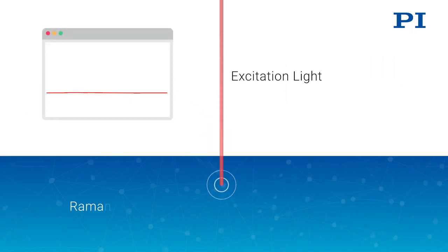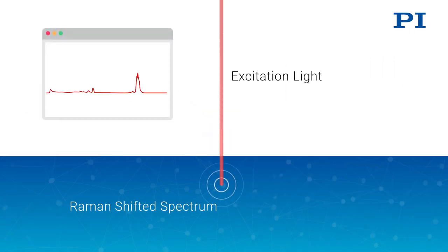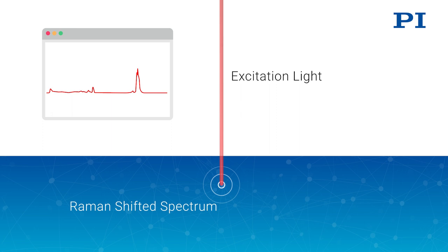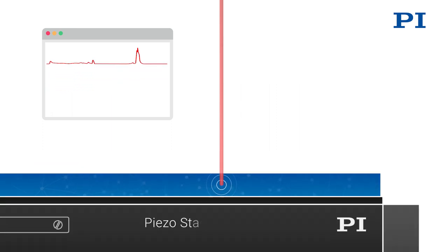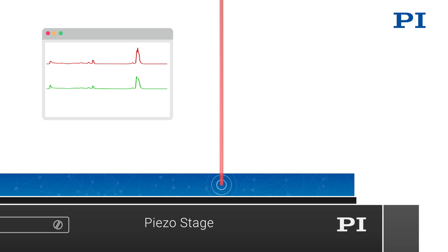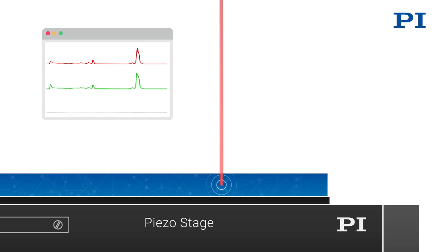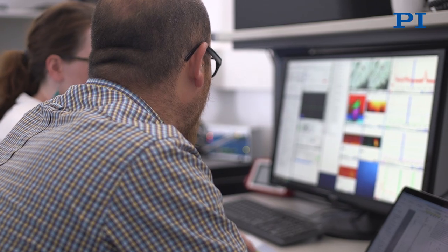In the case of confocal Raman microscopy, it is possible to achieve resolutions of 200 nm, but the stages must be able to achieve a resolution of considerably less than 100 nm. Capacitive sensors are also helpful in this case. For example, it is virtually impossible to achieve this with stepper motors.